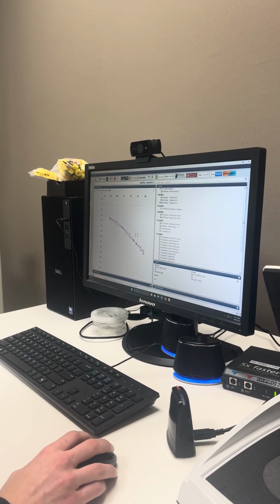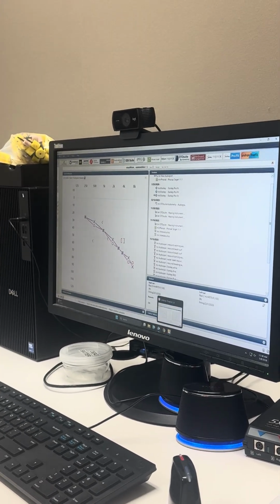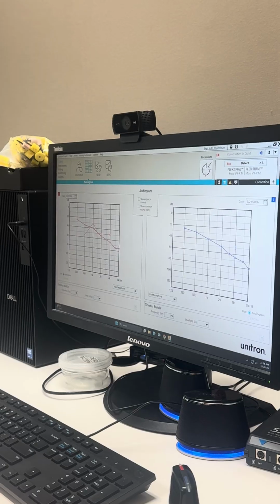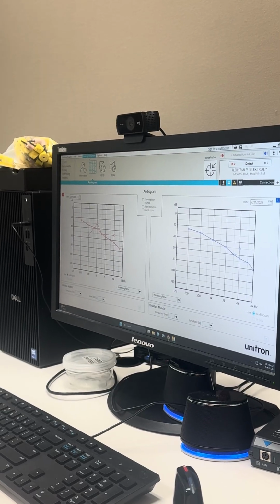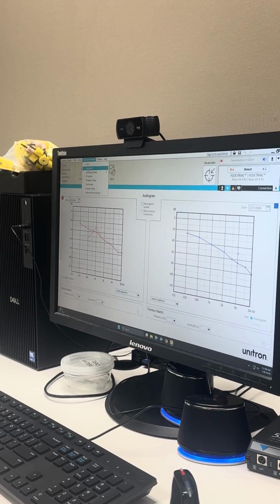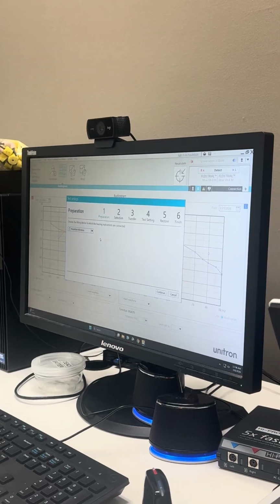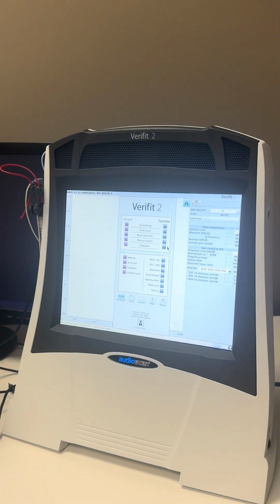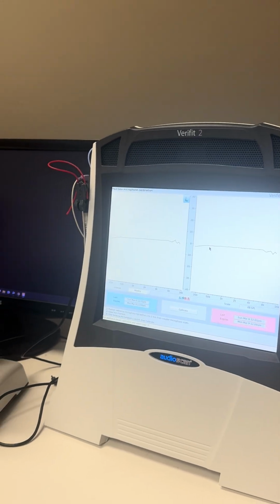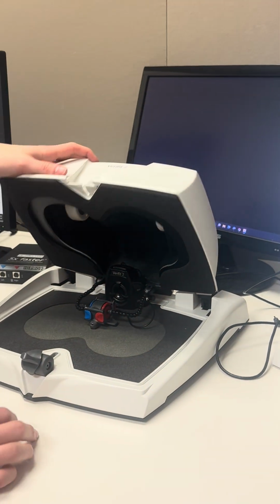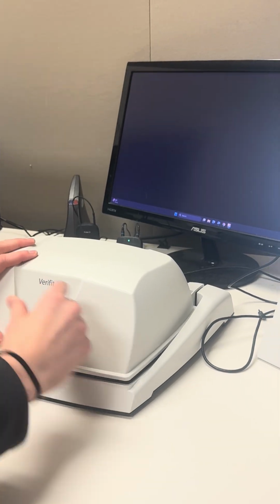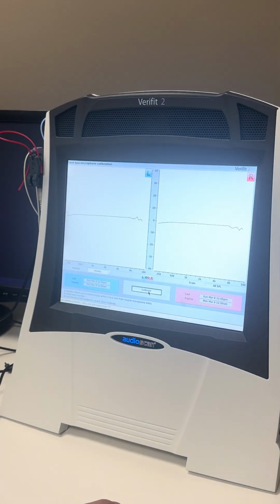All right, my patient is selected in NOAH here. I'm going to go to Unitron TrueFit software, and then under hearing instruments on top, I'm going to go to test mode. Before I do that, I'm going to set up my Verifit box with calibration by right-clicking, going to calibrate, and then I have my reference mics all set up for calibration. And then just click calibrate.